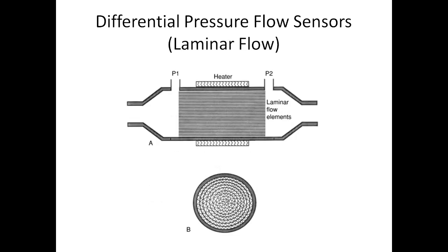Now let's move to a laminar flow style flow sensor. What they do is they have a series of tubules right here in the middle, which makes airflow linear, which is why it's laminar flow. On one side you're going to have a pressure measurement, and on the other side you're going to have a pressure measurement, because now you have a difference. As flow increases, it's going to get restricted because flow is normally turbulent. And since it's now going through a comb to straighten it out and make the air laminar, it's going to create a restriction, and that restriction is going to mean that there's now a difference of pressure.